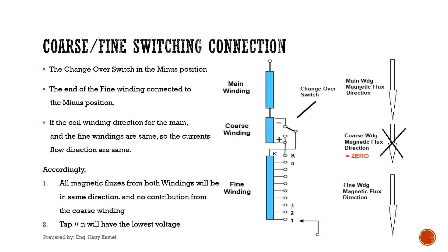But if the changeover switch is in the minus position, the end of the fine winding is connected to the minus position, so the coarse winding is excluded from the circuit. If the coil winding direction for the main and fine windings are the same, the current flow directions are the same. Accordingly, all magnetic fluxes from both windings will be in the same direction, with no contribution from the coarse winding. Tap number N will have the lowest voltage.